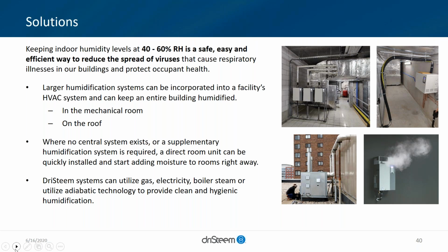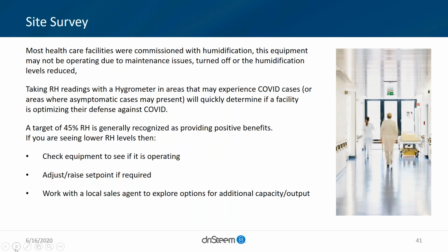We would recommend that any strategy starts with a site survey. Most US healthcare facilities were commissioned with humidification. This equipment may not be operating due to maintenance issues, may sadly have been turned off, or the humidification levels reduced - and we've seen examples in the letter from the three Boston area anesthesiologists.